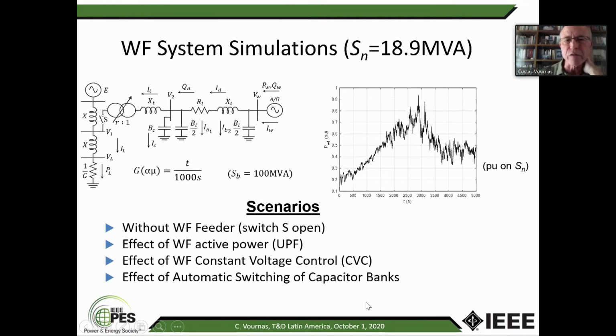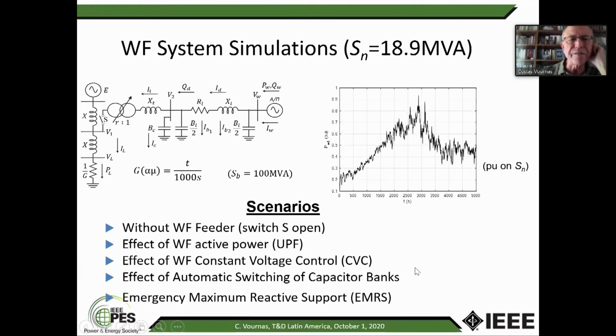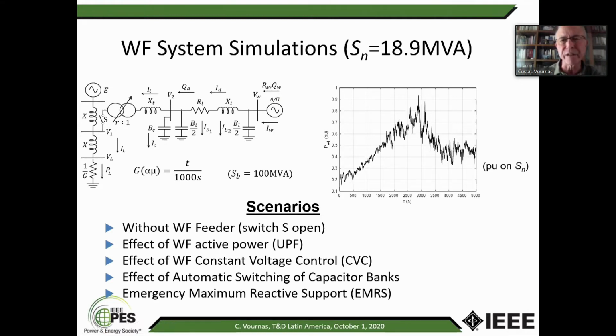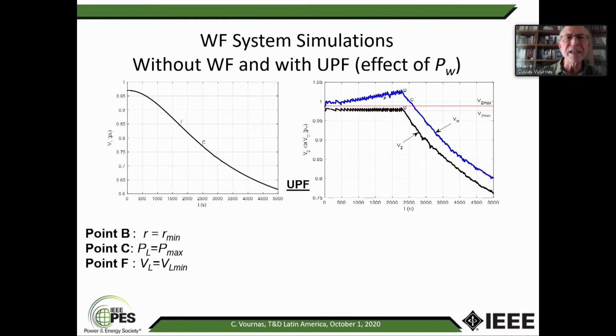Then we go to constant voltage control and the effect of capacitor banks. As I said, when the primary voltage drops, you have more capacitance, up to 3 banks. And finally, the emergency maximum reactive support. So here is the case of unity power factor, because we have the farm. The case without the farm will just be shown for comparison.